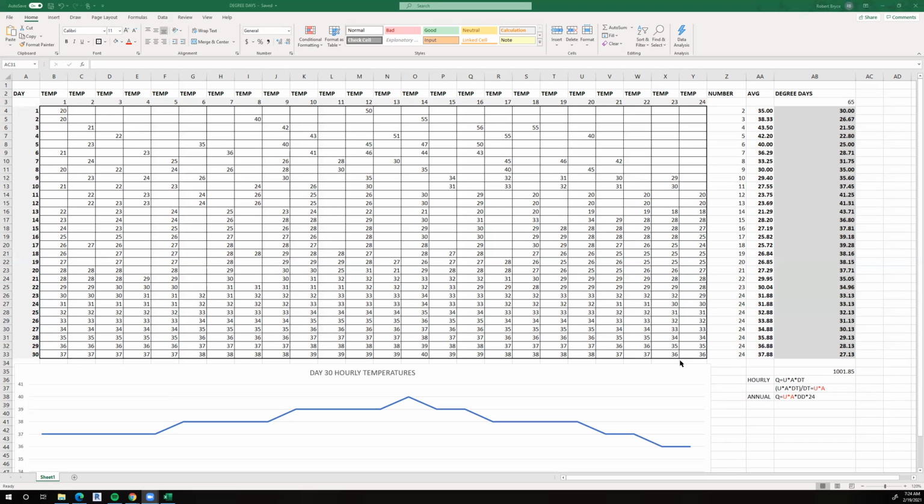Now, as Professor Bobker said in the third class, we don't actually calculate the degree days as individuals. Some government organization has done this for us for several years, for every single day. They may have taken four readings every hour, so their number is going to be even more accurate than ours would be if we calculated it ourselves. We go to a chart and find what the degree days for a particular area are. And that allows us to figure out what our annual heat loss is for a particular area based on the degree days of that area.